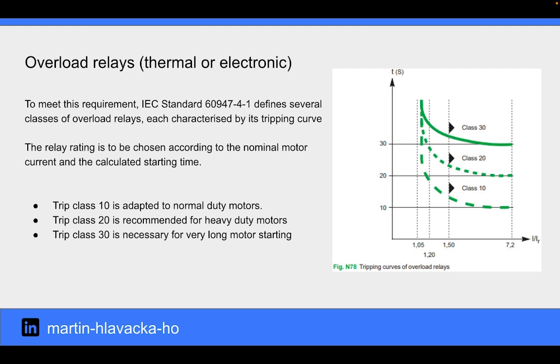To meet this requirement, IEC standard 60947-4-1 defines several classes of overload relays, each characterized by its tripping curve. The relay rating is to be chosen according to the nominal motor current and the calculated starting time. Trip class 10 is adapted to normal duty motors. Trip class 20 is recommended for heavy duty motors, and trip class 30 is necessary for very long motor starting.